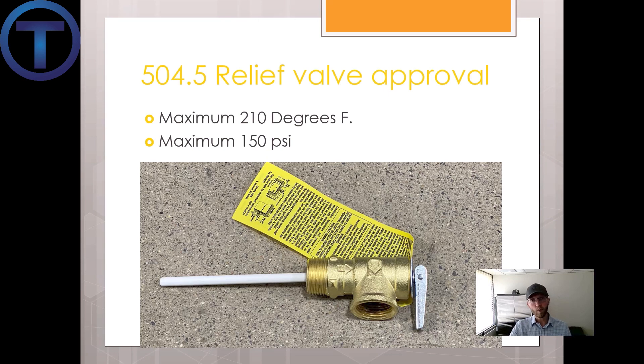Those are the two points at which the valve should open up. Most of the time it's going to open due to high pressure rather than high temperature, since we're almost at boiling at 210°F. You can get temperature pressure relief valves rated higher than 150 PSI — up to 170 or other ranges. They look and install the same. Let me tell you what plumbers used to do — and please, don't do this anymore.